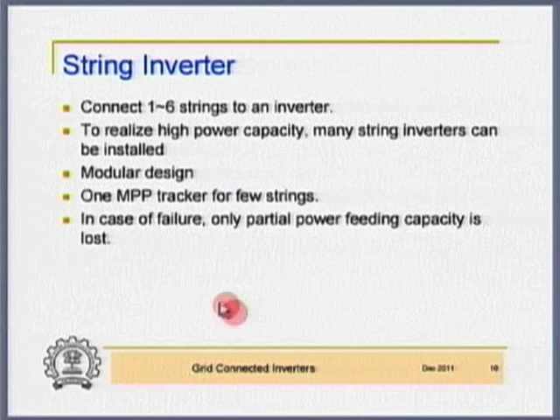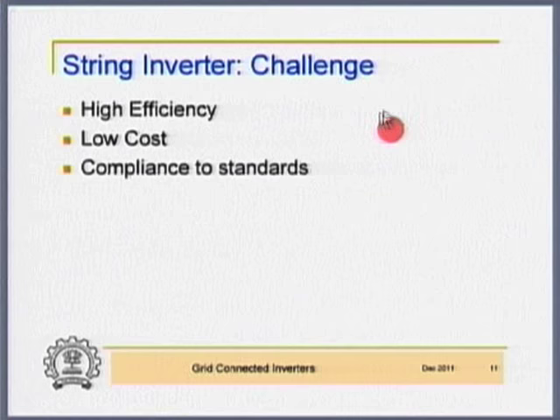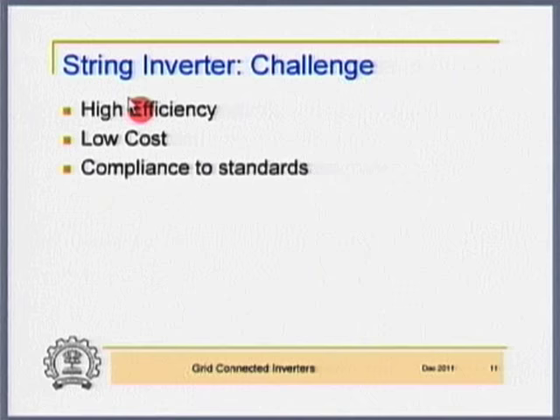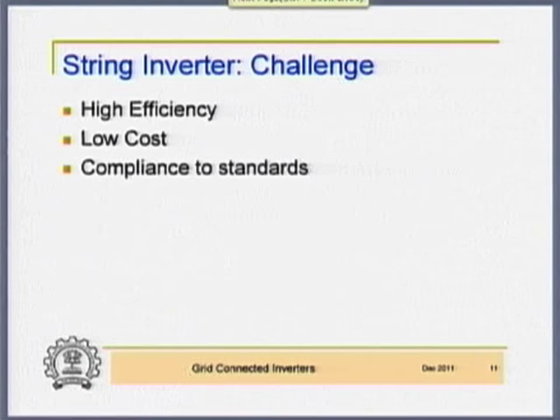Each group of 6 or 8 strings has one inverter, and there may be N such inverters. So if one inverter fails, only part of the capacity is lost — not the entire capacity as in the central inverter case. The challenges include: as the power rating comes down, maintaining efficiency becomes an issue. Also, low cost and compliance to standards — not only harmonics but also DC current injection to ground are issues.